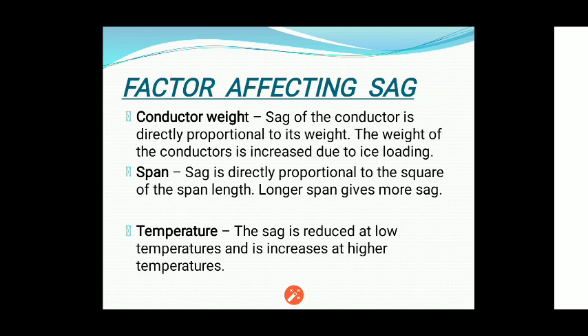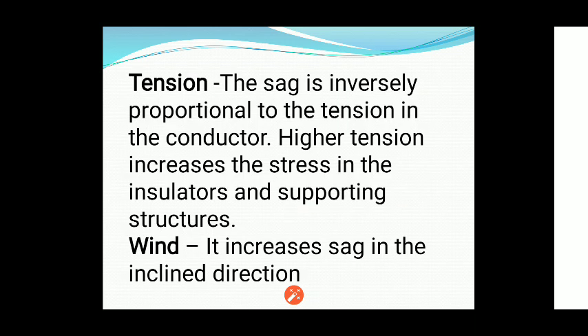The third factor is temperature, which is one of the most important factors. Sag is reduced at low temperature and increases at higher temperature. The next factor is tension — sag is inversely proportional to the tension in the conductor. Higher tension increases the stress in the insulators and the supporting structure.